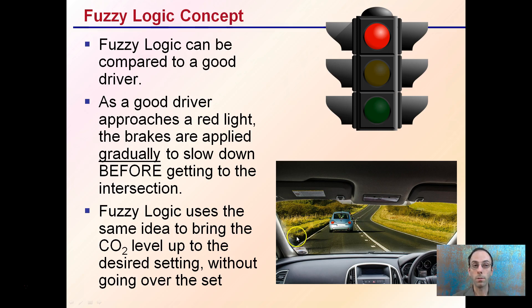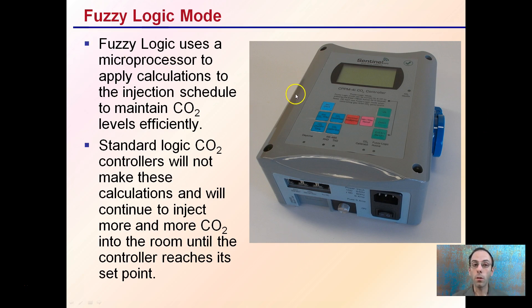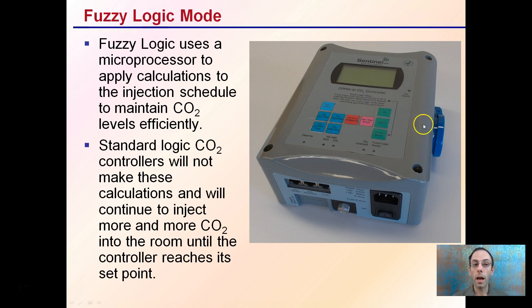This helps make them more efficient. Within the unit is a microprocessor that applies calculations to the injection schedule to maintain CO2 levels efficiently. Standard logic controllers will not make these calculations and will continue to inject more and more CO2 until the room reaches the set point, then turn off. If the air wasn't mixed properly, that can cause an overshoot, then a drop, then continued injecting — which can cause issues. Having this microprocessor applying calculations ensures that the CO2 added to the grow room is added efficiently based on calculations of conditions over time.